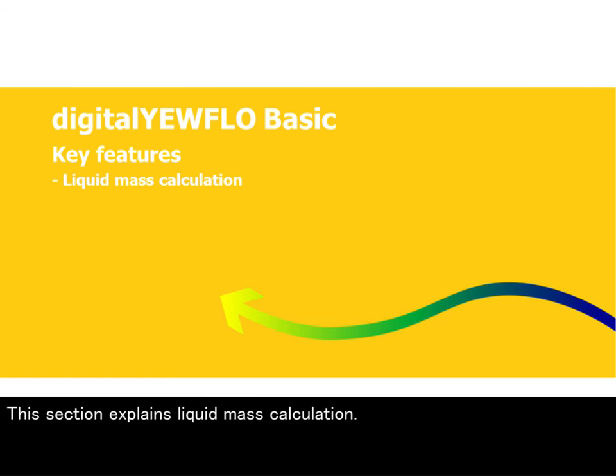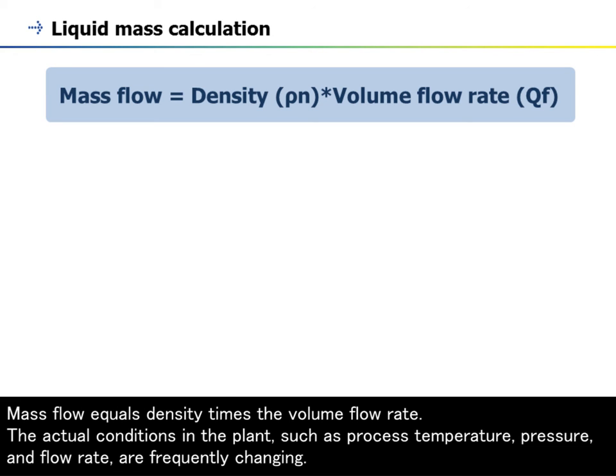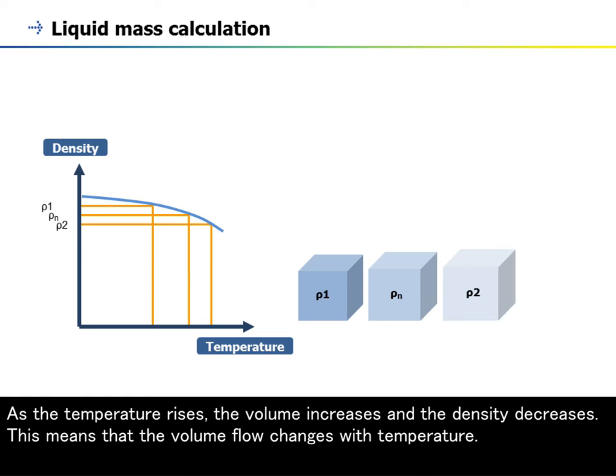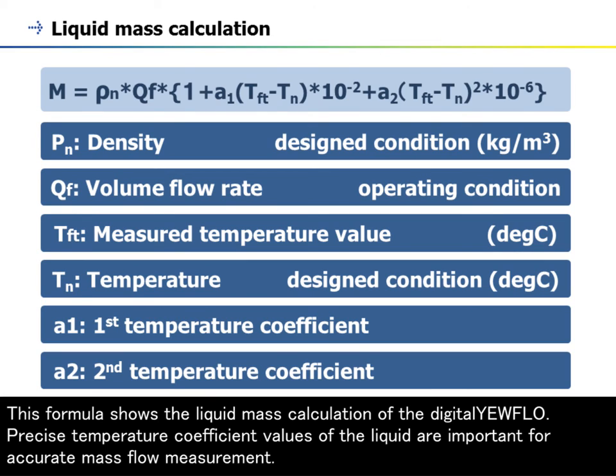This section explains liquid mass calculation. Mass flow equals density times the volume flow rate. The actual conditions in the plant, such as process temperature, pressure, and flow rate, are frequently changing. This graph shows the density versus temperature of a liquid. As the temperature rises, the volume increases and the density decreases. This means that the volume flow changes with temperature. If we measure liquid mass flow, we can compensate the volume flow. The density of the liquid is compensated per the measured temperature value. This formula shows the liquid mass calculation of the digitalYEWFLO. Precise temperature coefficient values of the liquid are important for accurate mass flow measurement.